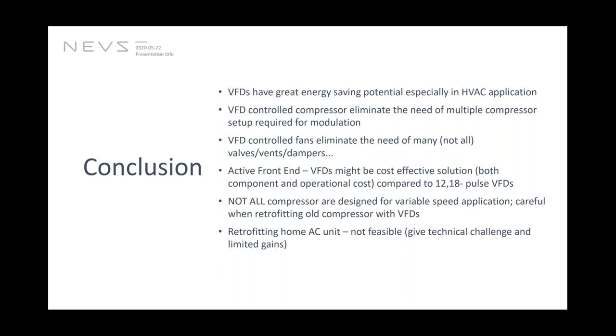the annual energy bill. Another thing that I concluded is that a VFD-controlled compressor eliminates the need for multiple compressors, which are there to modulate between full load and part load application. And a VFD-controlled fan will also eliminate quite many, if not all, valves, vents and dampers used to control the flow rate in the HVAC application. The thing that I could mention is that active front end VFDs might be a cost-effective solution, both unit price component-wise and operational cost, compared to 12 and 18 pulse VFDs.